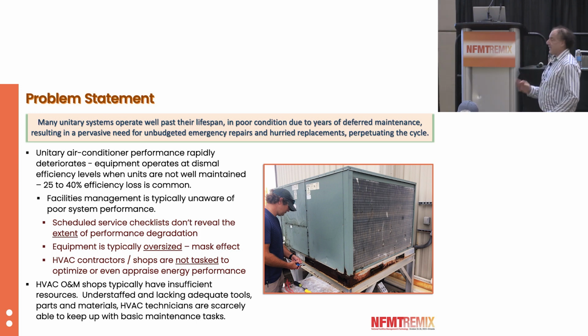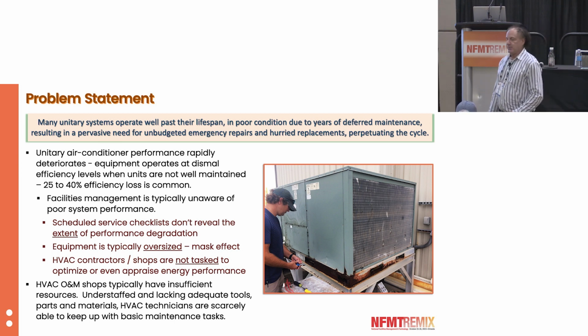So what that causes is, as the unit loses efficiency over time, say the condenser coils corrode, things come out of adjustment, it's not really noticed. The occupants don't notice because there's enough extra capacity to make up for it. And the service techs don't notice because they're not really trained. It's not really part of their service protocol to check the performance. I mean, as long as the occupants are cool and the system is working, that's usually good enough.